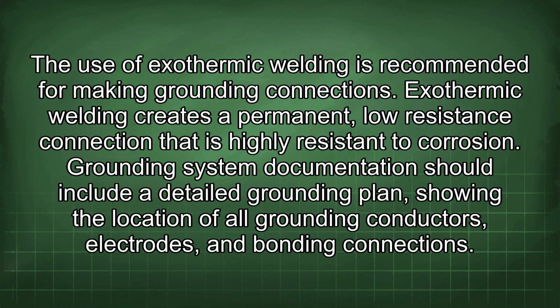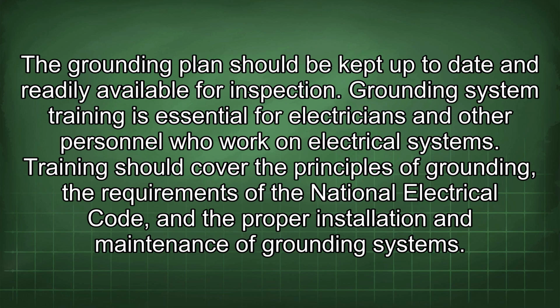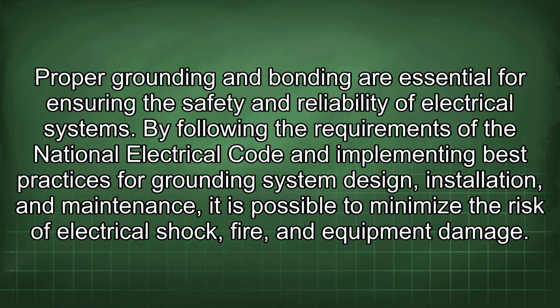Grounding system documentation should include a detailed grounding plan, showing the location of all grounding conductors, electrodes, and bonding connections. The grounding plan should be kept up to date and readily available for inspection. Grounding system training is essential for electricians and other personnel who work on electrical systems. Training should cover the principles of grounding, the requirements of the National Electrical Code, and the proper installation and maintenance of grounding systems. Proper grounding and bonding are essential for ensuring the safety and reliability of electrical systems. By following the requirements of the National Electrical Code and implementing best practices for grounding system design, installation, and maintenance, it is possible to minimize the risk of electrical shock, fire, and equipment damage.